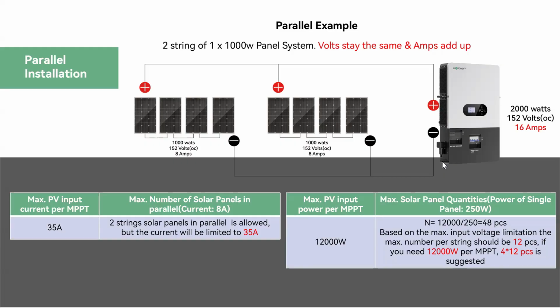And the question from Jimmy: can the inverter run without battery during power interruption? Yes, our inverter can run without the batteries, just through PV. If the PV input is within, for example, the 100 to 480 volt range, we can run the inverter just on PV or just on the grid without the battery, like traditional string inverters.